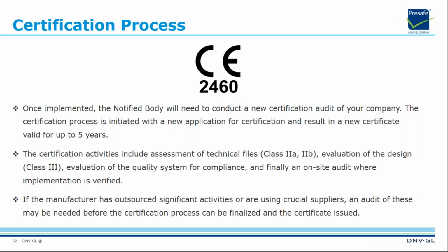For the certification process, once the requirements of MDR are implemented, the notified body will need to conduct a new certification audit of your company. The certification process is initiated with a new application for certification and results in a new certificate valid for up to 5 years. Actually, according to the regulation, all certificates after May 2020 must be based on MDR, so based on new agreements and new certificates.